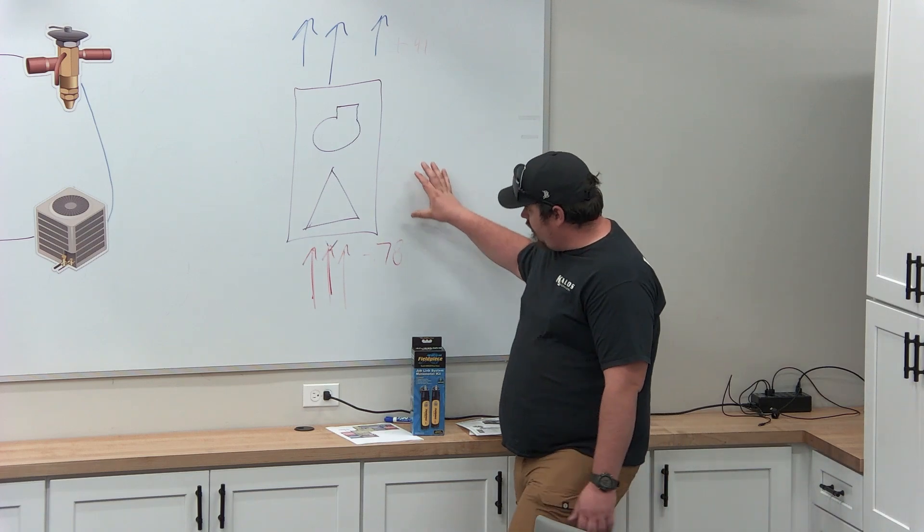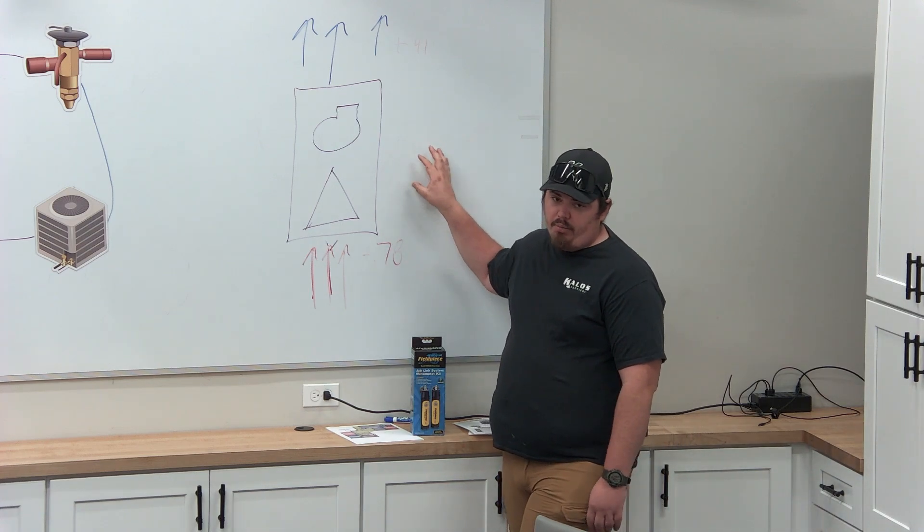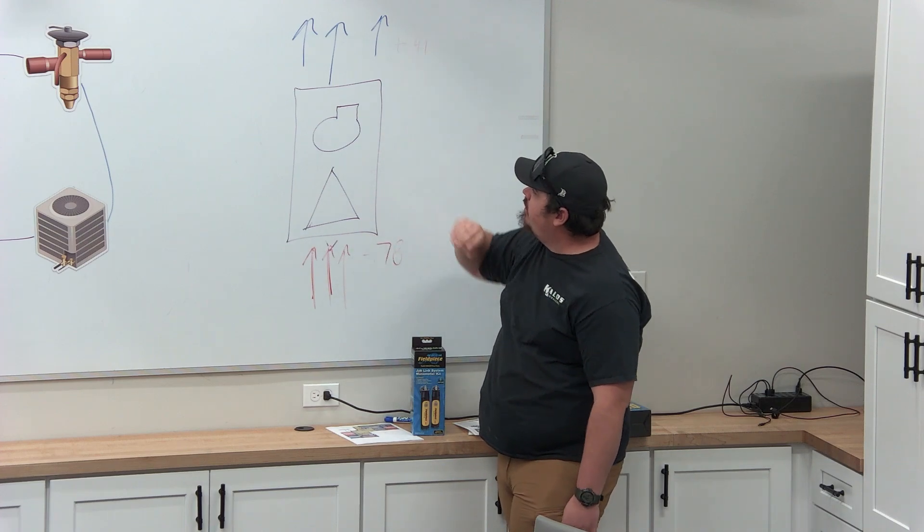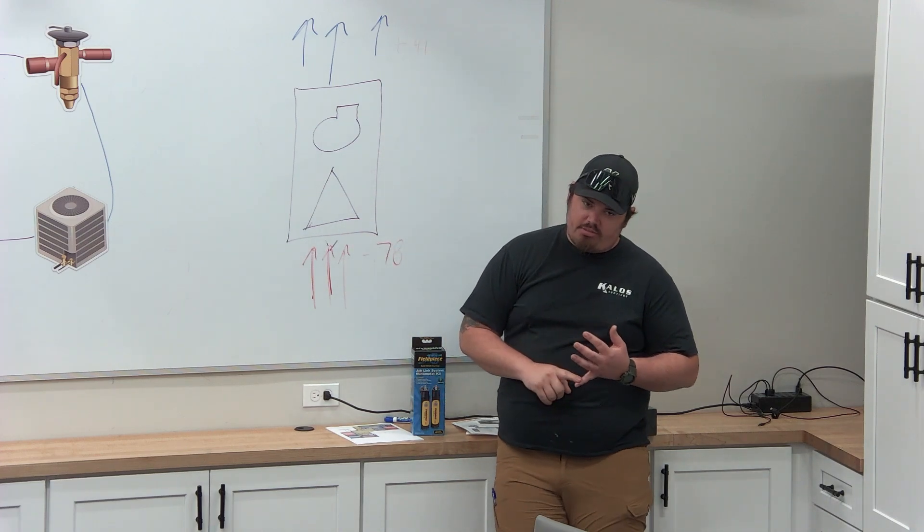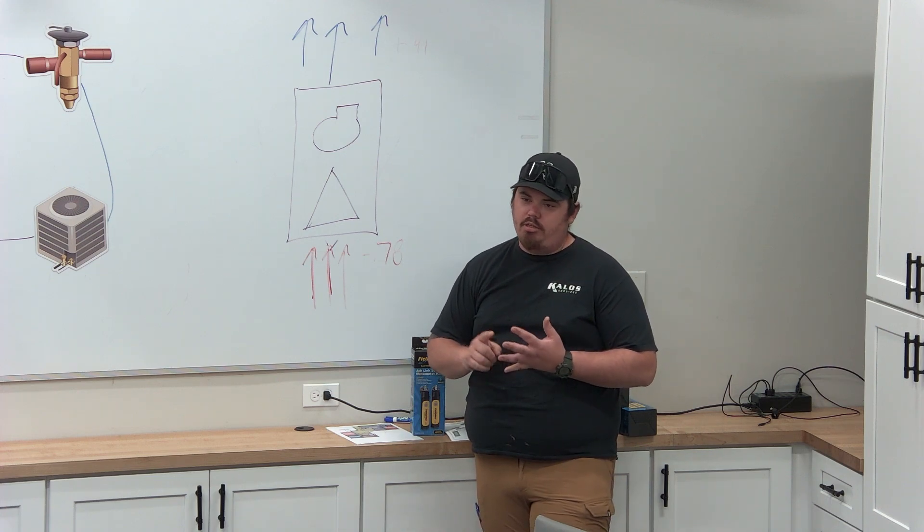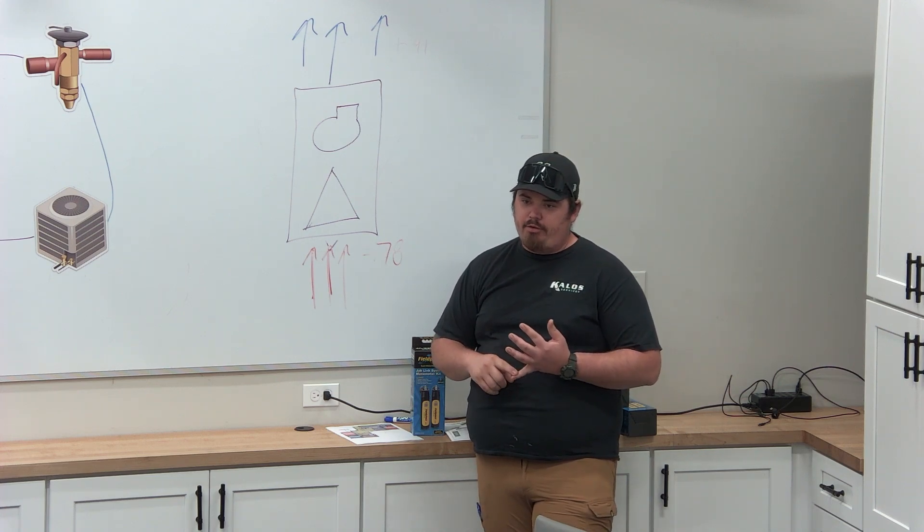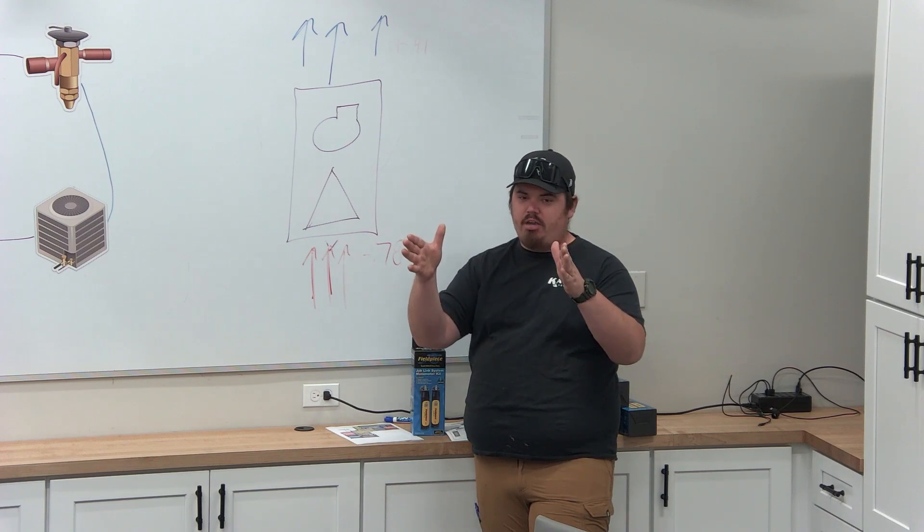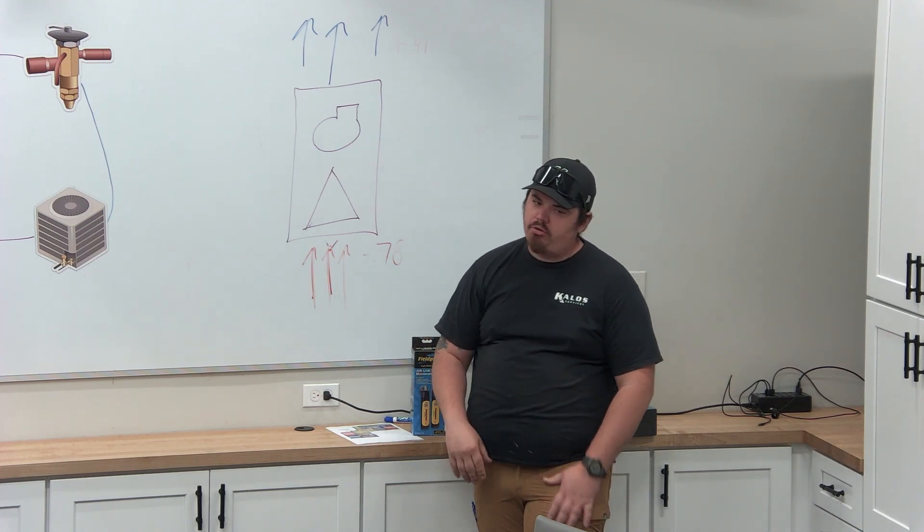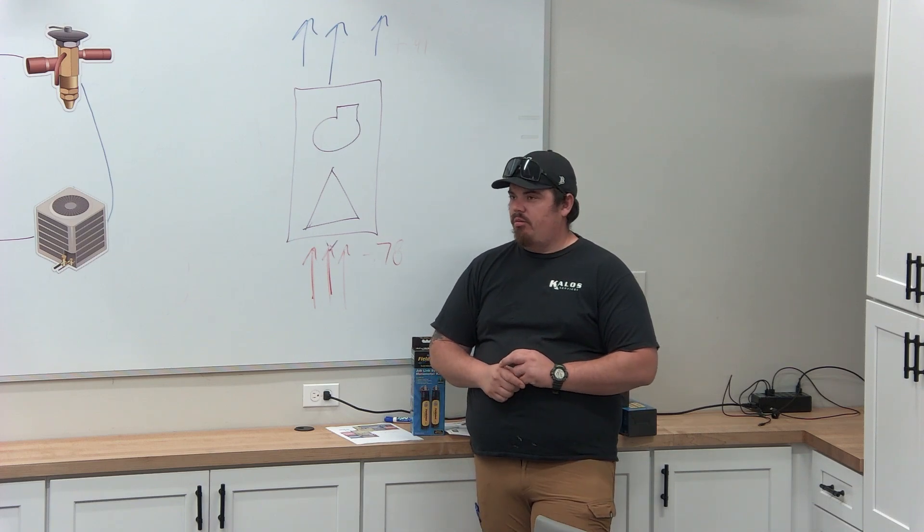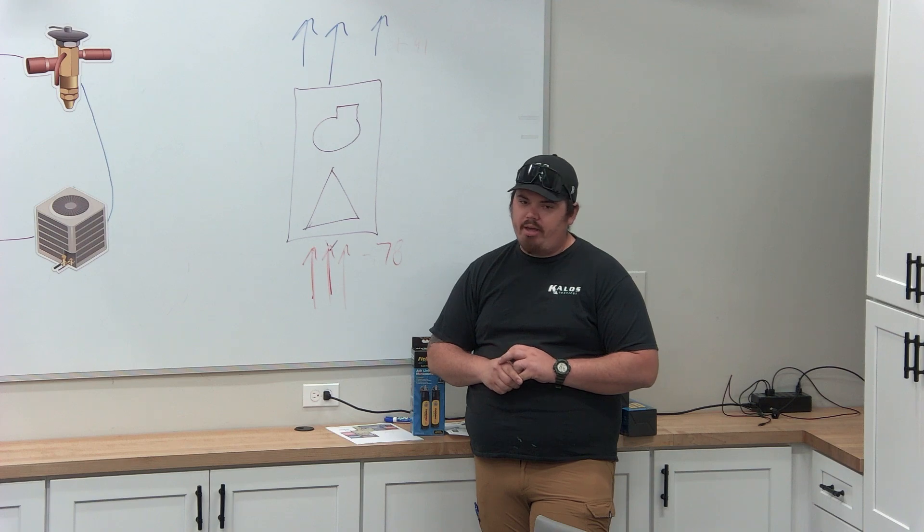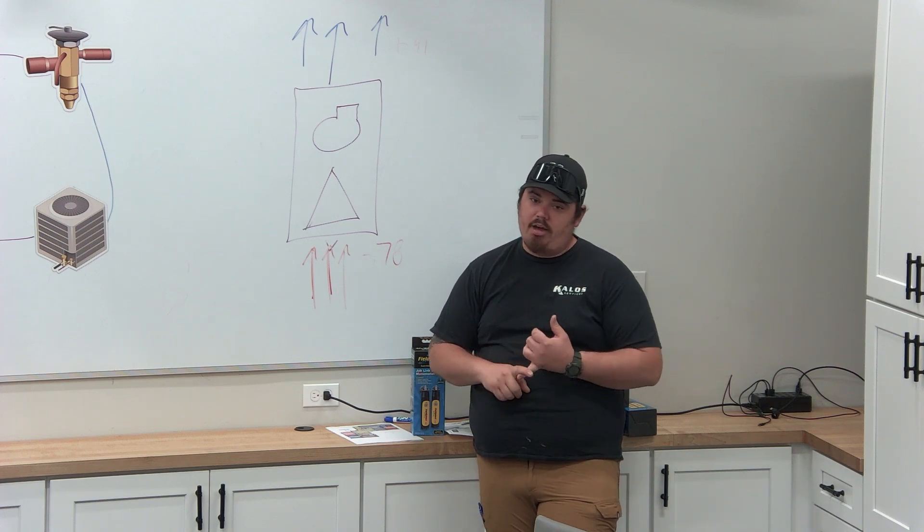So what this is telling us is we've got a really big problem on both sides of the system, essentially on the return and the supply side. So now we start to understand the importance of not just attic inspection, is it sealed, is it strapped? Look at that flow. Where's my first takeoff, and where does this go? Do we have bad pinches? Do we have crushed ductwork? Talk to the homeowner, oh, I just had a plumber and electrician up there. You know how that conversation is going to go. Hey, you've got a lot of issues up here.